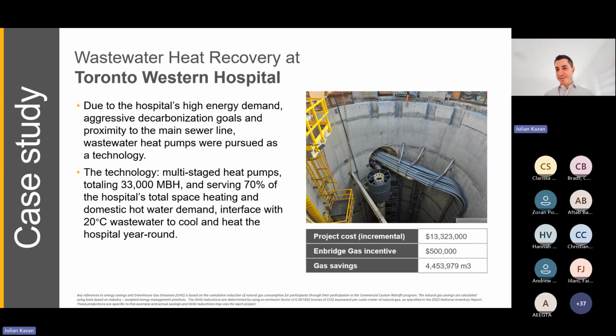The benefit of that is that the wastewater sewer line, you can't really freeze it. There's so much energy in there that it's like limitless for the hospital to interact with, as opposed to the ground, where you have to watch how much you're interacting with it when doing a geothermal system. Wastewater is also 20 degrees Celsius year round, as opposed to the ground that's like 8 to 10 degrees Celsius, so you get some benefits on the COP and efficiency of the heat pumps.